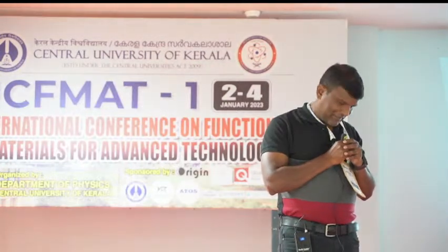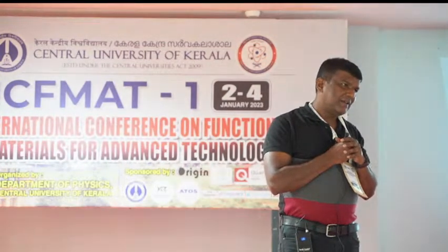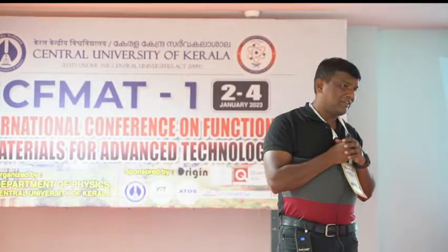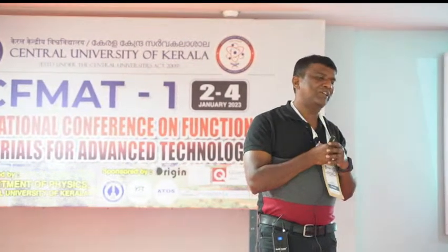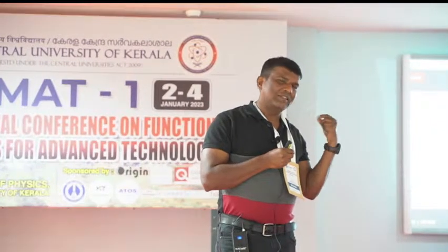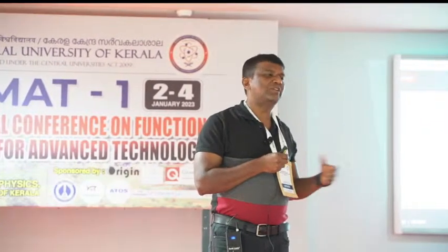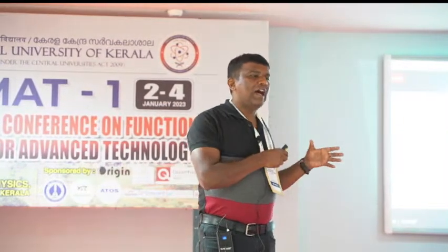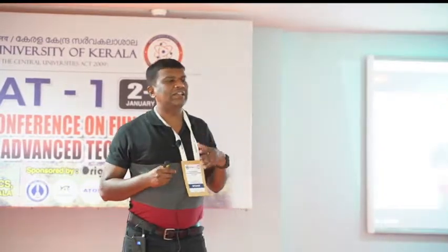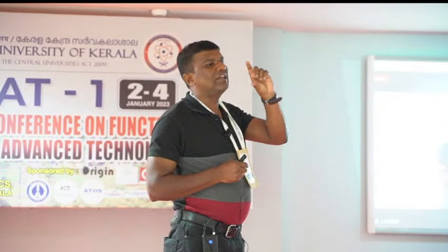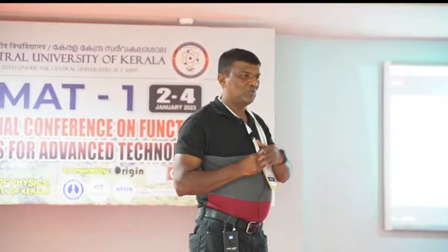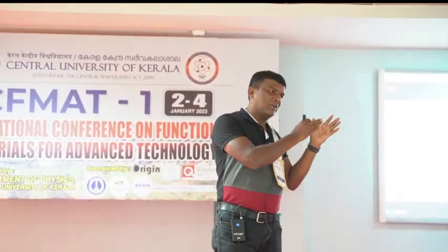I work with virus, so that's why. Another question, the integration of this system with the inverted microscope, the normal optical microscope. The one that is coming will be compatible with an inverted microscope. The one you're going to install newly, right? That is supposed to come now. That is possible to combine with an inverted microscope. But the one you already have also has the possibility to combine with something called a digitally inverted optical microscope, where you can use only a single objective at a time. So you can use a single objective, take an optical image. That option is possible with the system that you already have.